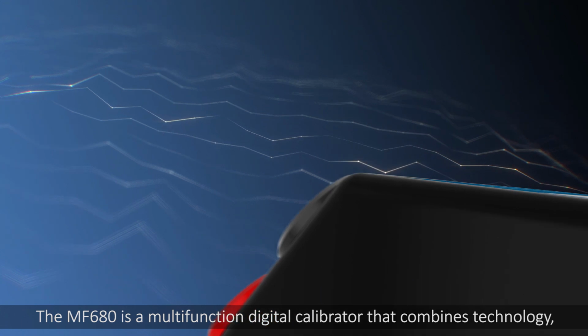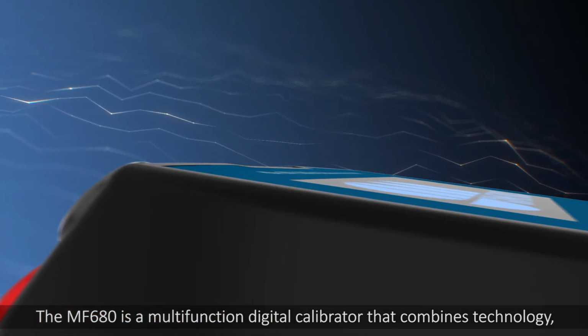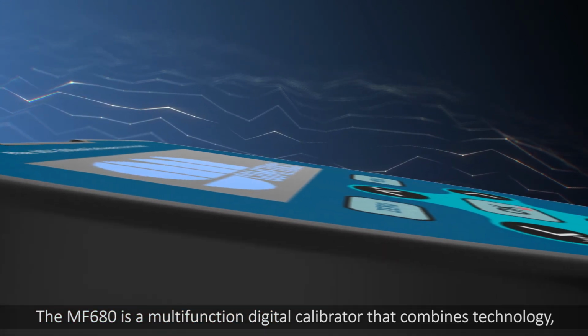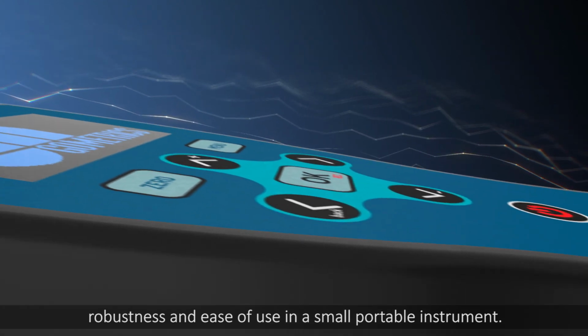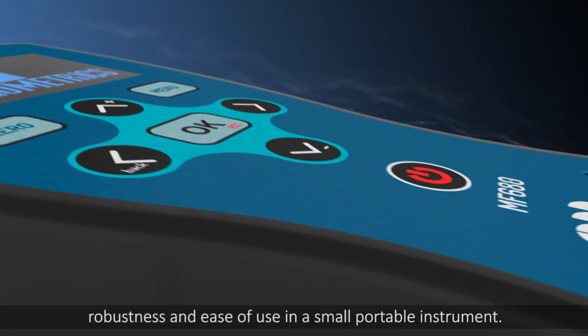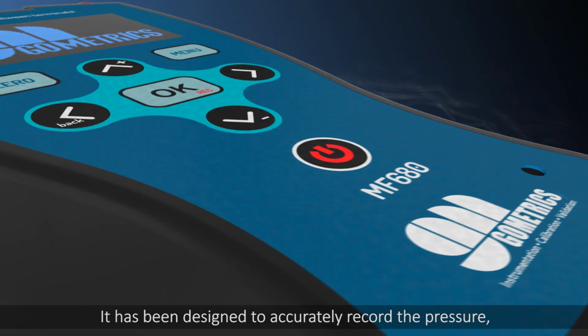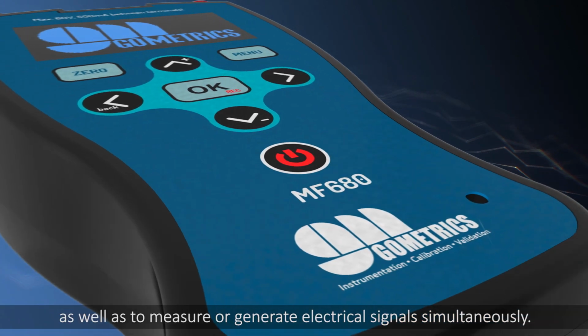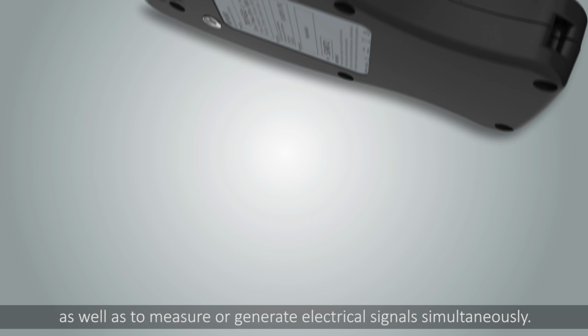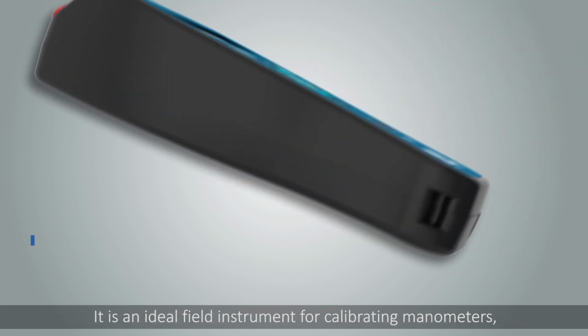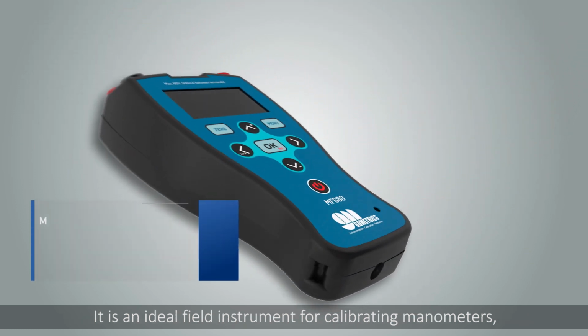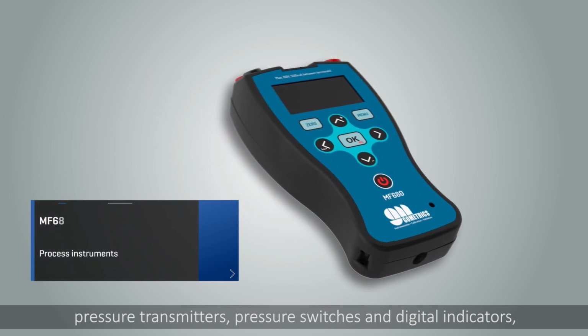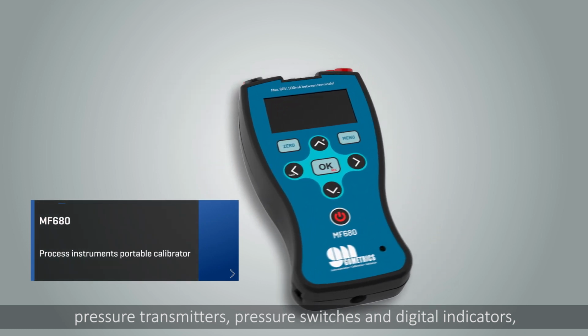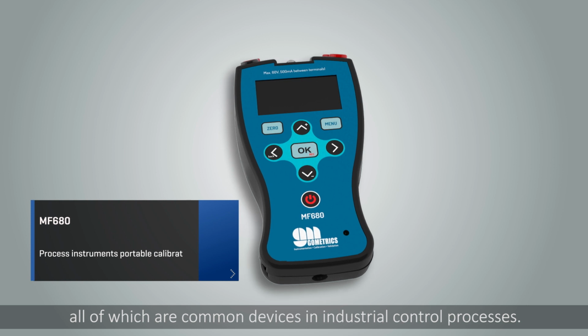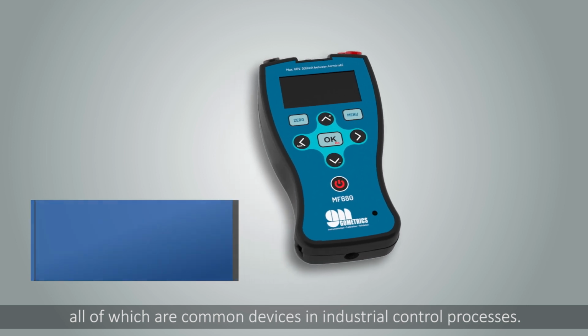The MF680 is a multifunction digital calibrator that combines technology, robustness and ease of use in a small portable instrument. It has been designed to accurately record the pressure as well as to measure or generate electrical signals simultaneously. It is an ideal field instrument for calibrating manometers, pressure transmitters, pressure switches and digital indicators, all of which are common devices in industrial control processes.